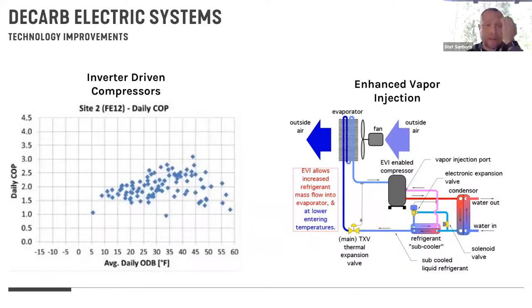The graph on the right is a DOE cold climate study where they were looking at standard compressors versus inverter-driven compressors. What they're essentially showing is that most of the state-of-the-art inverter-driven compressors, like mini split systems on the residential scale up to VRF, are able to do a pretty good job maintaining COP and output down to that 5 degrees, 0 degrees temperature before they have to boost on into some of the electric resistance backup elements.